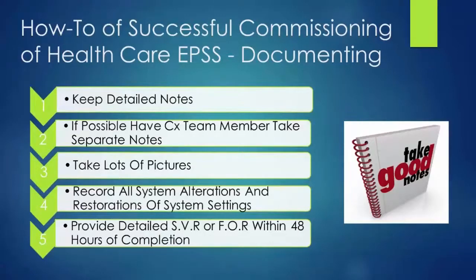Record all system alterations and restorations of system settings. This is very important. The paralleling gear and the emergency power supply system is designed to operate in a specific way. And when we're testing it, we're changing a lot of settings in the system, and we're asking it to do different things so that we can check all of the programming and functionality of the system. It's very important that before you start testing, you make sure that this is the system of operation as it's supposed to be.